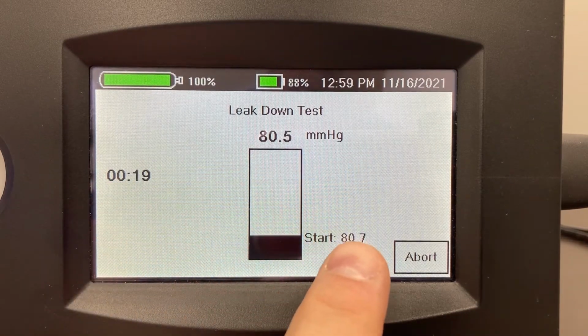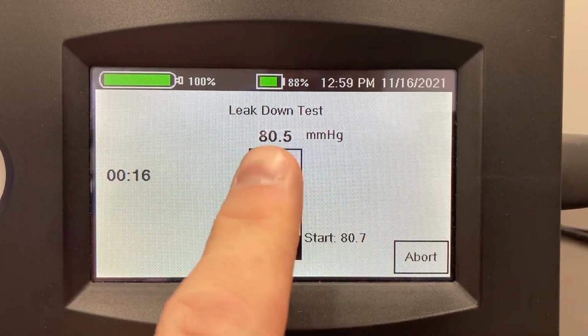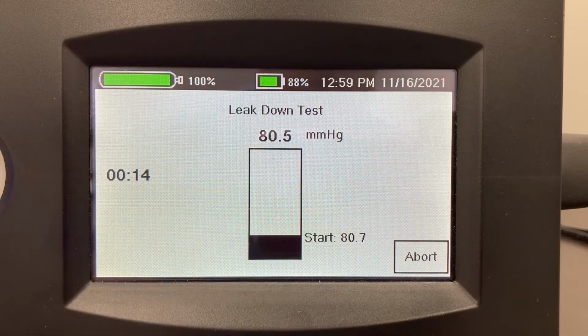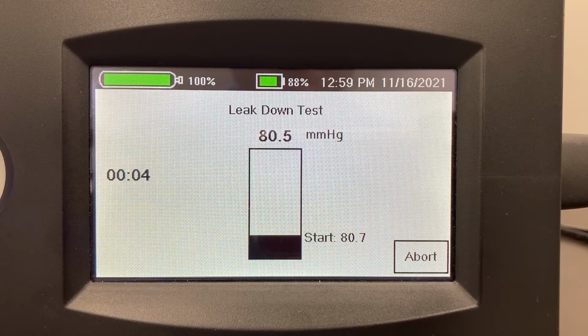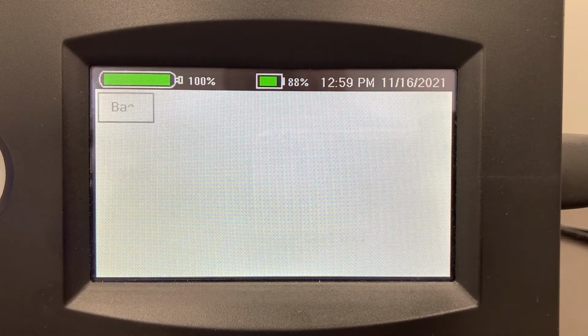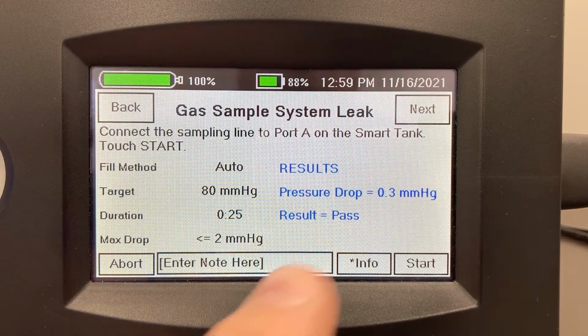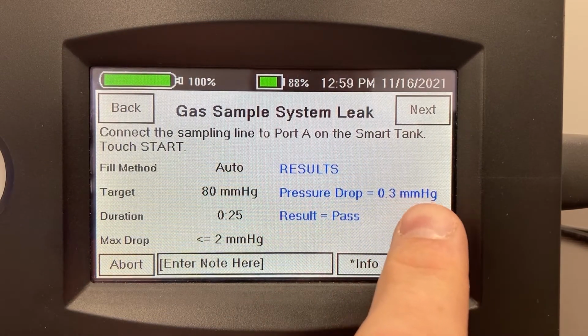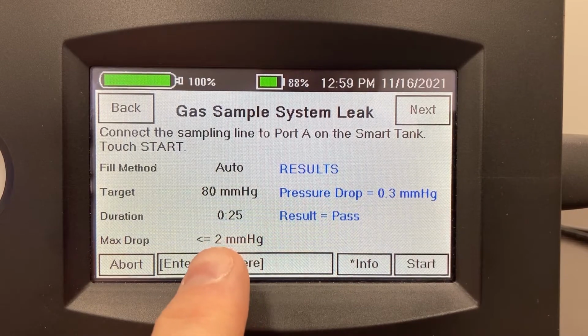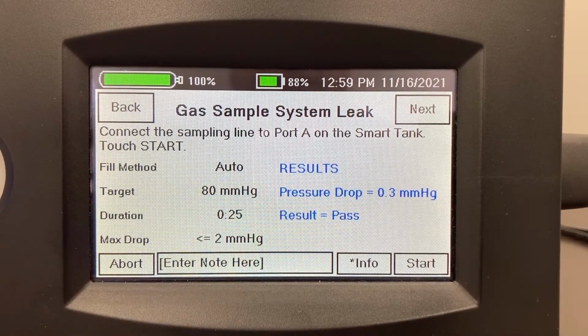The starting pressure was 80.7. We can watch what the actual current pressure is to see if it's leaking. Pretty much everything you test will have some tiny leak rate. But you can see that this one's not leaking very much. So the actual pressure drop was 0.3. The service manual said it could drop up to 2 millimeters of mercury, so it passed very well.